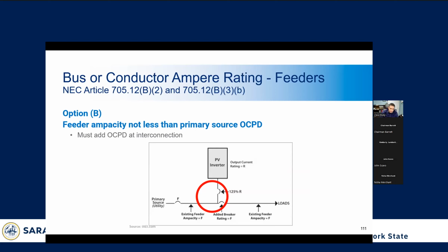Here we have what's called a feeder tap, and they're a type of interconnection that requires special consideration. It's sort of like a hybrid load side connection. They have the potential to add additional available current to conductors and bus bars, and you have to consider this when you're looking at this design. In this case, in order to protect the conductors from the additional PV current, an additional overcurrent protection device has to be installed. So this is the added breaker that they put in. And this is covered in Article 705 of the code.